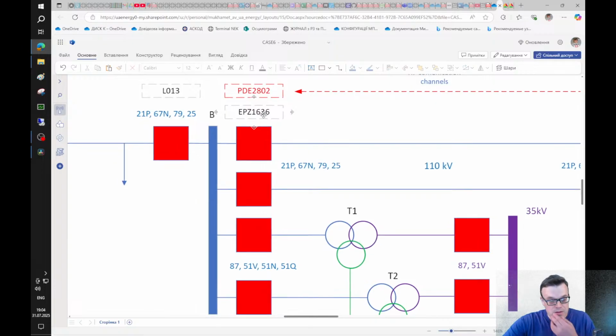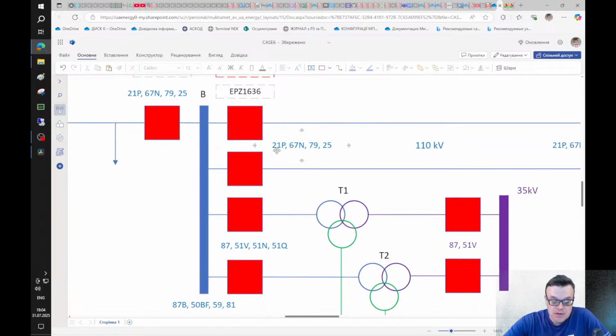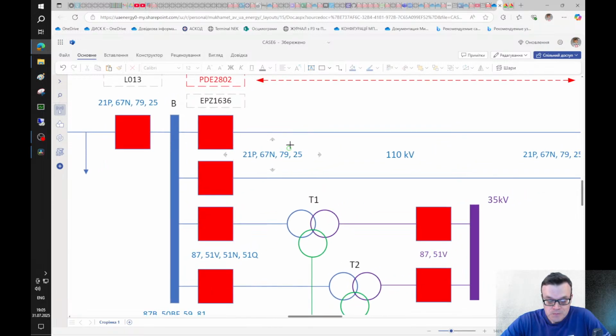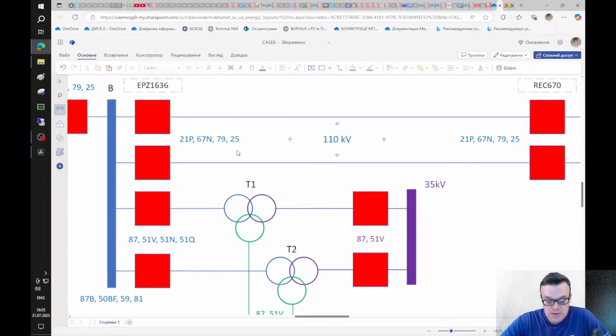Also there is a Soviet electromechanical panel that includes the functions described here: distance protection for multi-phase short circuits, overcurrent ground protection for single phase short circuits, also automatic reclosing and synchrophase check.